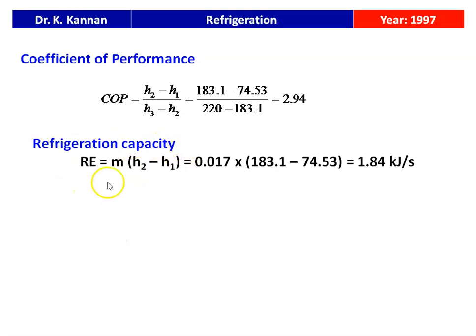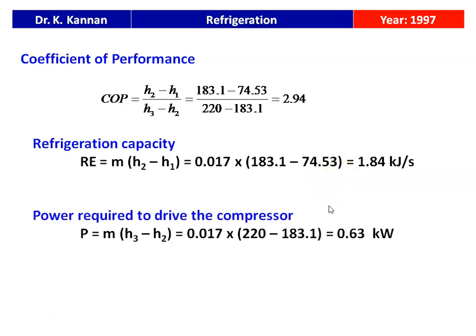Refrigeration capacity equals M multiplied by (H2 minus H1): 0.017 multiplied by (183.1 minus 74.53) equals 1.84 kJ/s. Power required to drive the compressor equals M multiplied by (H3 minus H2): 0.017 multiplied by (220 minus 183.1) equals 0.63 kilowatts. Summary: COP equals 2.94, refrigeration capacity equals 1.84 kJ/s, and compressor power equals 0.63 kW.